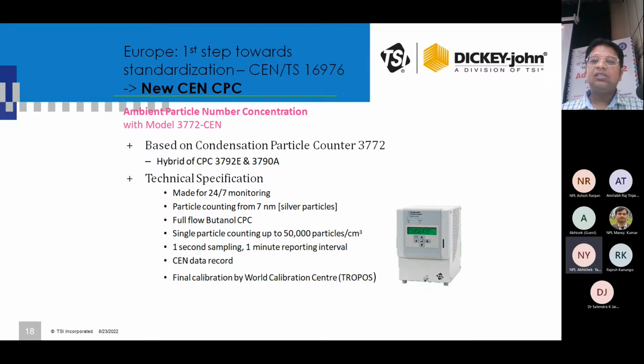Then it's a CPC. Earlier we talked about the different networks used across the globe. The ACTRIS network, the latest one, has recommended the CEN CPC to be used in the network. What is the CEN CPC? Normal CPCs are calibrated using PSL particles or salt solutions. This particular CPC, the CEN CPC, is calibrated using silver particles.